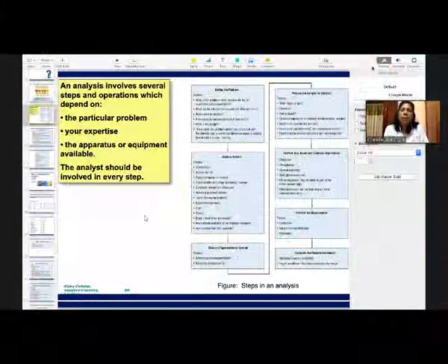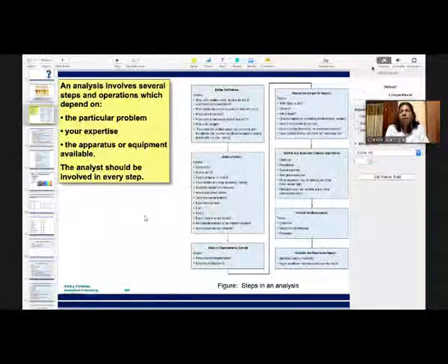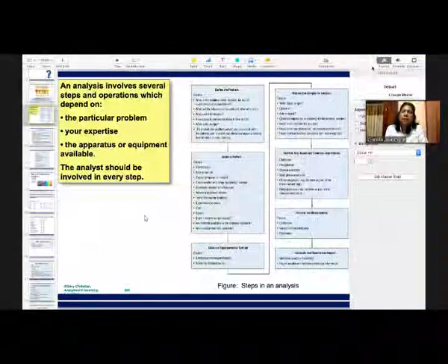Also, for validation, sometimes the company people come and validate the machine. In that situation they use standards, not the compounds, as the standard, and they validate it. So validation is really important. Similarly, we validate the pH meter and the analytical balance, and sometimes thermocouples, and they can be adjusted. We validate the oven too: in the case of an oven, the temperature inside may not be 40, so they adjust it and validate it. So those validations are really important.